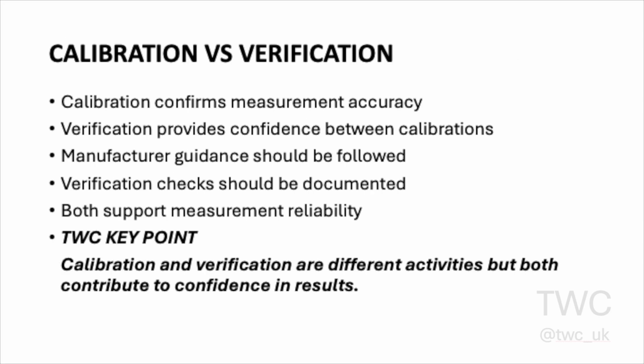Calibration and verification are often confused, but they are not the same thing. Calibration is intended to confirm the accuracy of an instrument against a recognised reference standard. Verification is generally a routine check carried out between calibration periods to provide confidence that equipment remains suitable for use. Both processes are important and both contribute to confidence in the measurements being recorded.